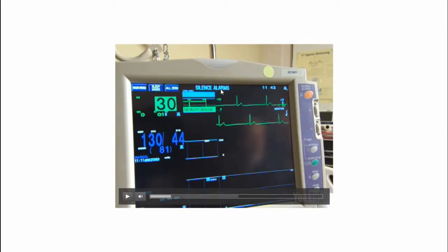And if we look at it, it's not really clear that the alarm has been silenced. If you were standing 20 meters away, could you see it? If you were standing 5 meters away, could you see it? At the end of the ward, would you be able to see that? So the way this information is displayed on here, although useful in some respects, has got some faults. One way that we could fix this, my idea I think, would be to change the background color from black to a red maybe, to show that this alarm has been silenced, and then you wouldn't even need that there as such. That would just mean the alarm is silenced. It wouldn't just be relying on that text and that little icon in the corner.